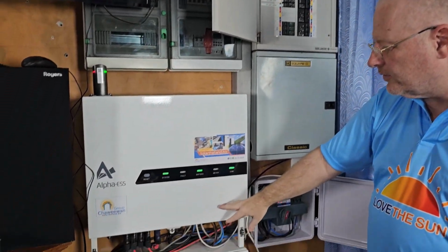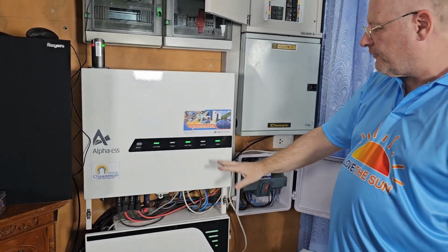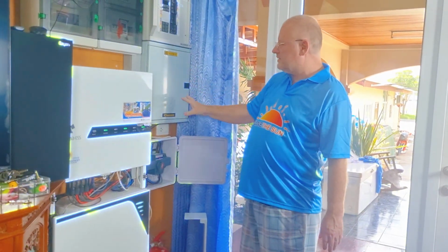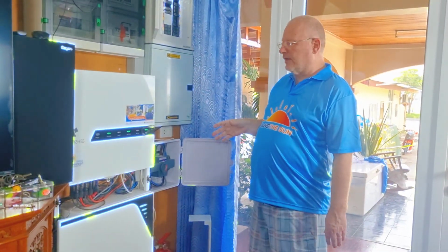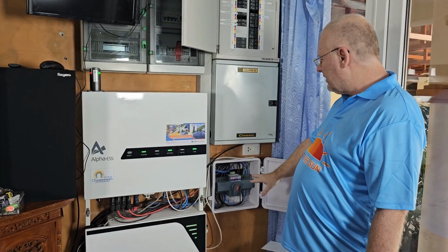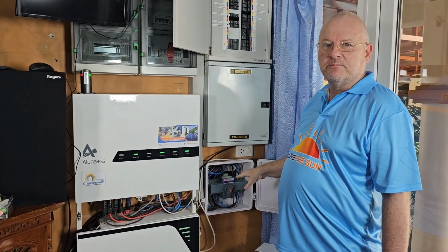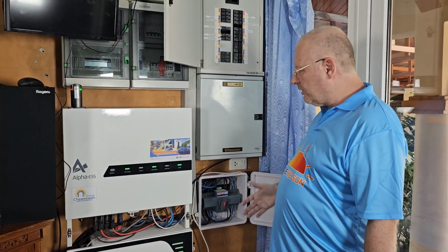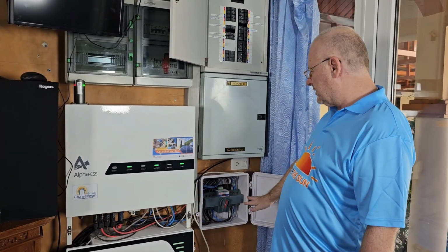The inverter is doing the switching. It's switching from the grid side to the backup side, giving power to the UPS, and now we are not connected to the grid at all. This is the way that it should be. So the ATS right now is not working, and that's the main point to remember, that in a normal functioning power cut, the ATS is not switching.